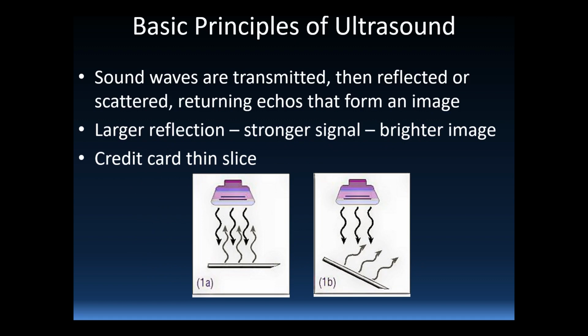Essentially the transducer emits sound waves that enter the body, hit a structure, and then are reflected back to the transducer to form an image. The larger the reflection is, the stronger the signal, and therefore the brighter and clearer the image is. So you want to be right on top of the structure of interest. It's also important to remember that the beam of sound waves emitted is only as thin as a credit card slice. Although the transducer is quite thick, about 2 to 3 centimetres, it's really only a credit card thin slice. This is really important when you start moving the ultrasound probe on your patient's arm, in that very small movements can cause quite big differences in your picture.